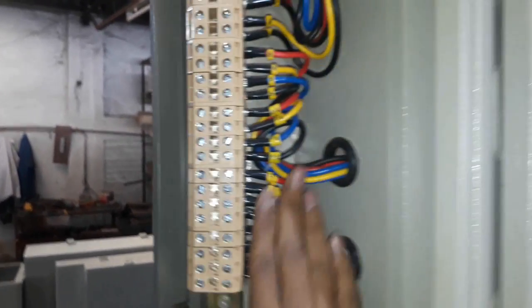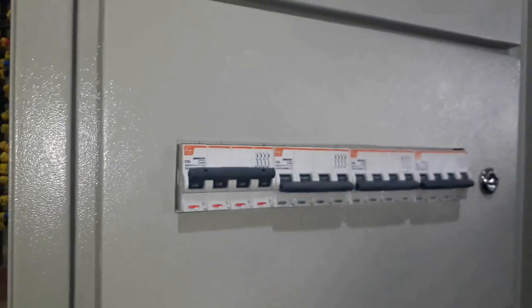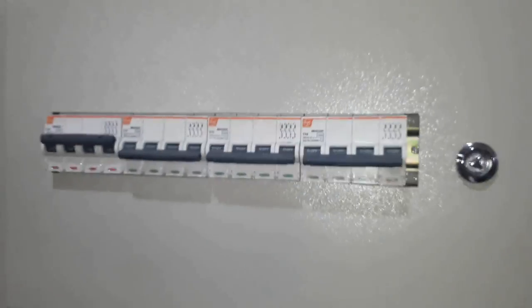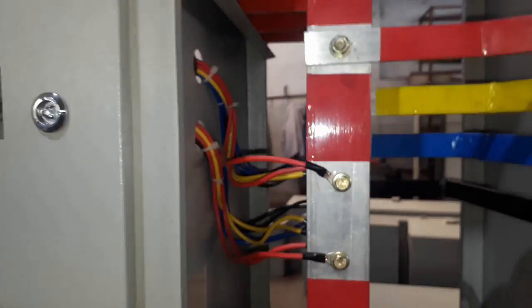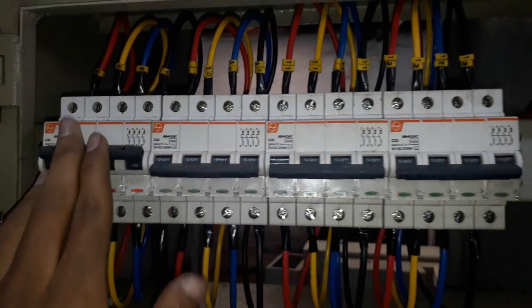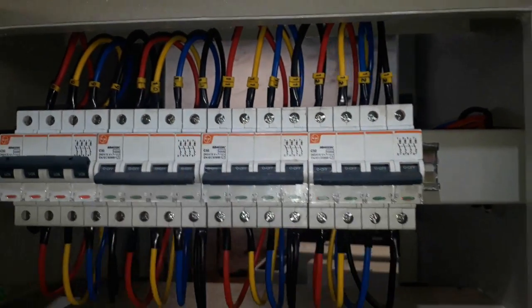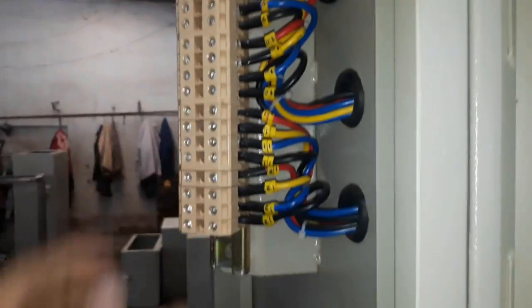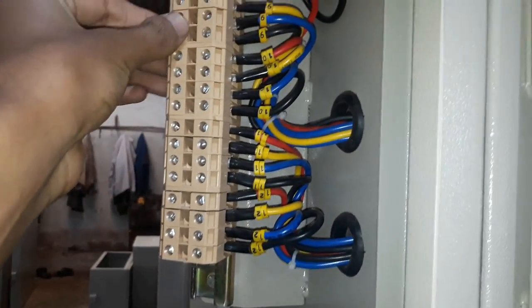Here you can see these are 4 circuit breakers, 63 ampere 4 pole circuit breakers. We are taking a cable from this bus bar chamber for supplying the power to the phase in of these 63 ampere circuit breakers. The phase out of these circuit breakers are connected to these terminal blocks present here. These are 4 wire 3 phase terminal blocks.